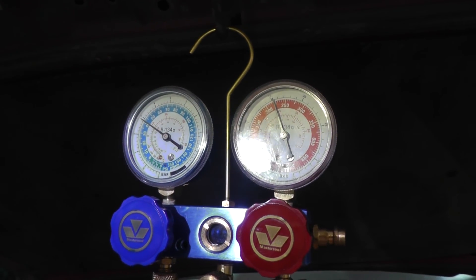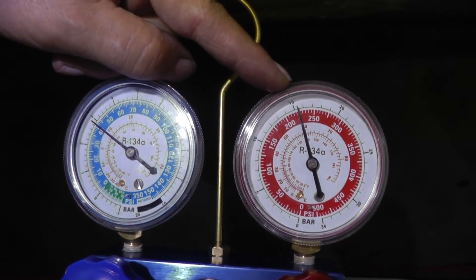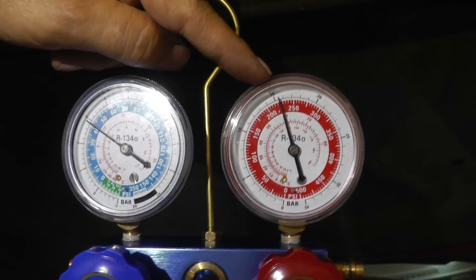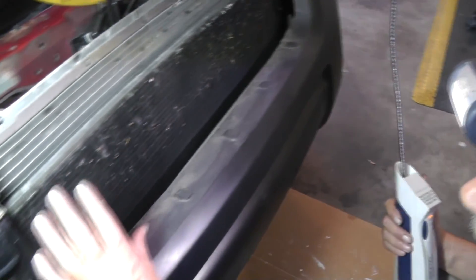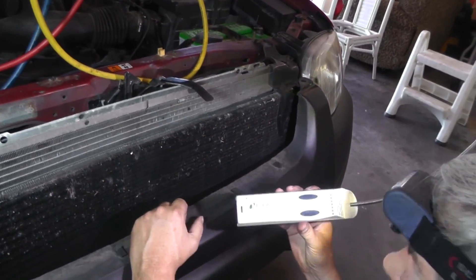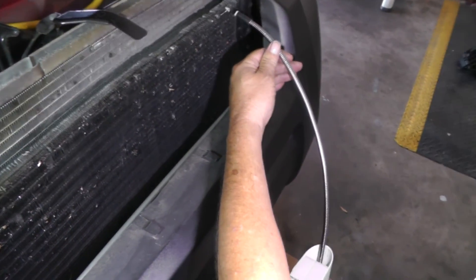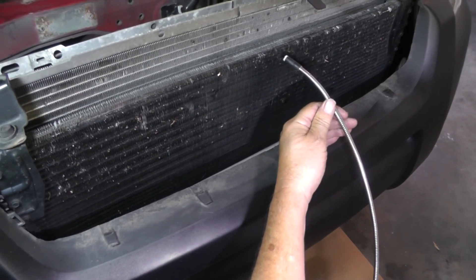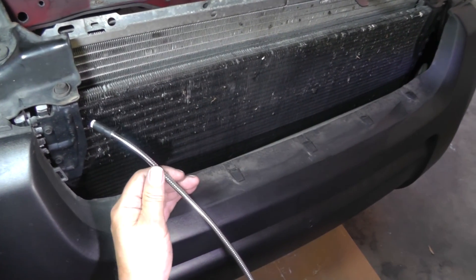Let's go ahead and look for some leaks. I want to take advantage of this high head pressure of 225 psi and look at the condensing side. I've removed the front grill to expose more of the condenser. I'm using an electronic leak detector made by Inficon — the D-TEK Select. You want to hold it about a quarter inch away from where you suspect a leak and move across slowly so it can sample the air. This detector has an internal air pump sampling continuously.